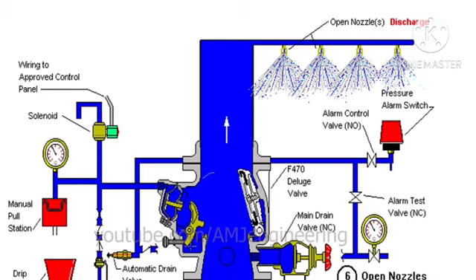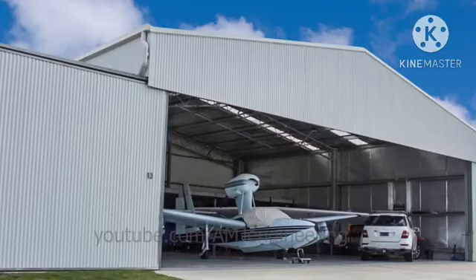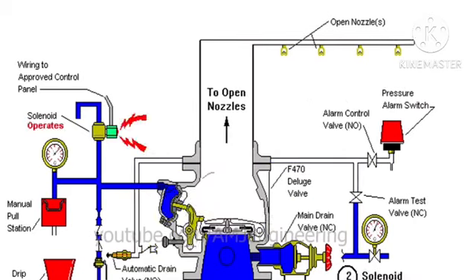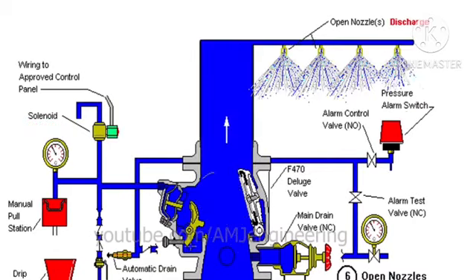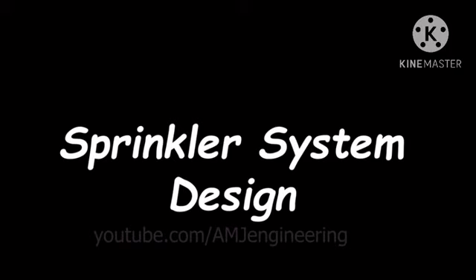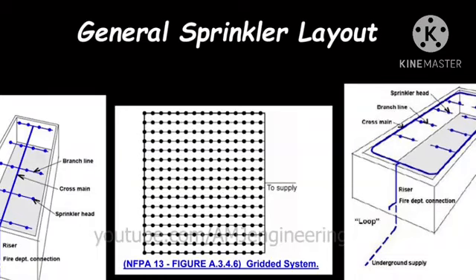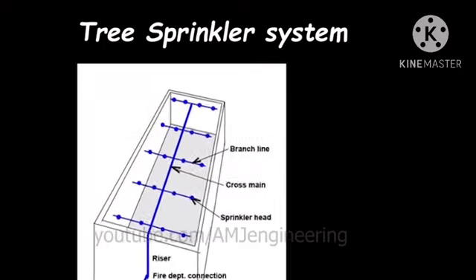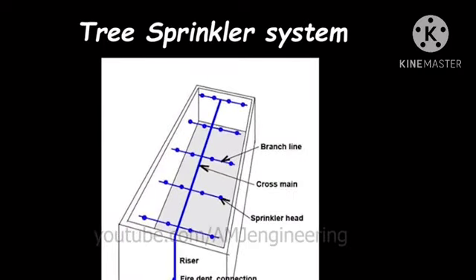An important consideration in the selection of the type of sprinkler system is the level of hazard being protected. If protecting an area of very high hazard, such as aircraft hangars, a deluge system may be the most suitable. Automatic sprinkler system design. The layout of fire sprinkler systems is usually one of the following. Tree sprinkler system. It is the normal design system, and it consists of a main pipeline with branches on both the left side and right side.